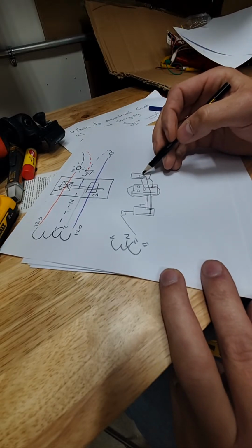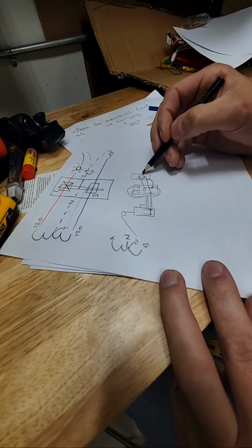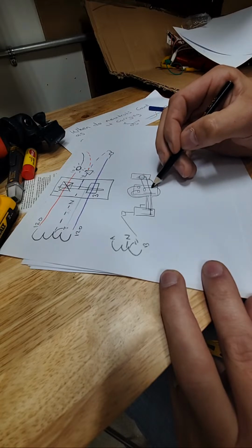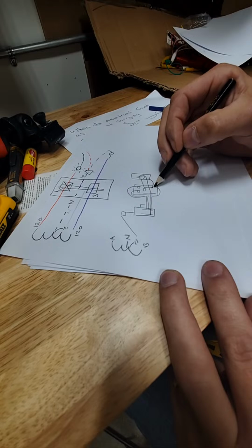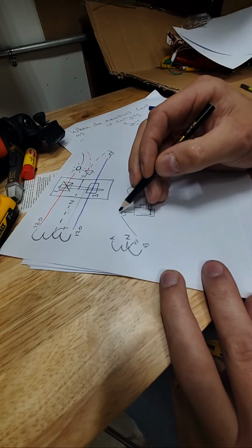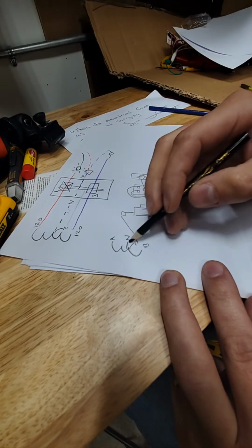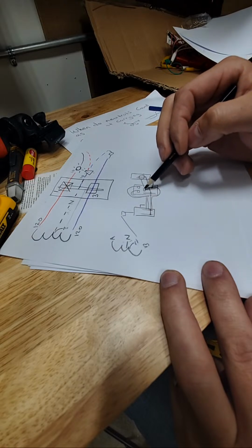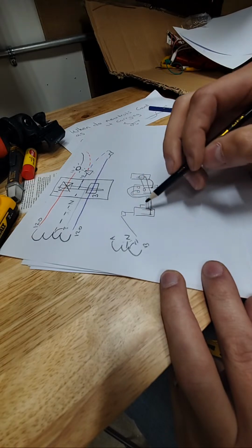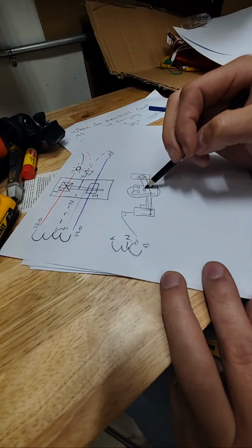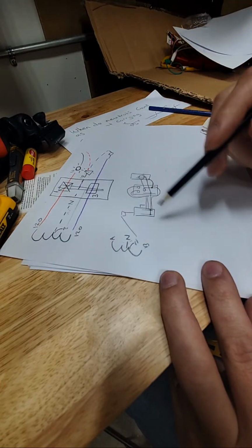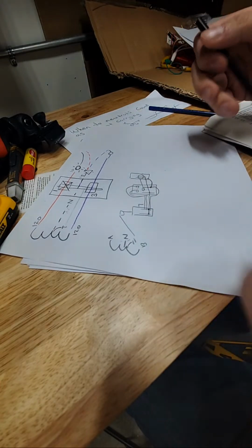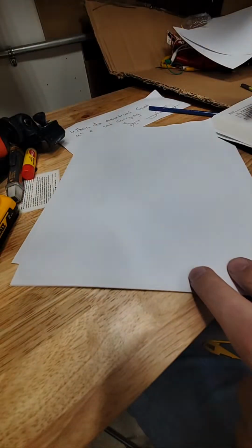What happens is when you have a fault, the current gets on the case, gets to the ground, and gets on the neutral, and then goes back through the windings of the transformer, comes back on the hot, finds that breaker and trips it. You can't trip a 20 amp breaker based on 25 ohms to ground. So that's how all that works. 120. I told you I was going to explain it. There you go.